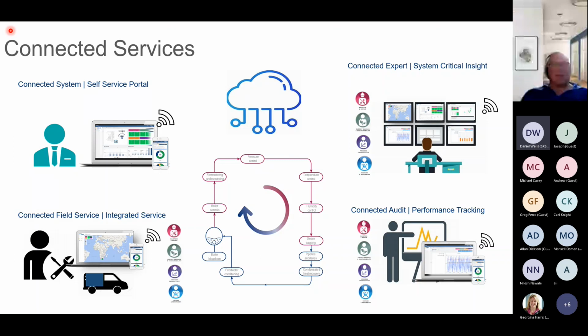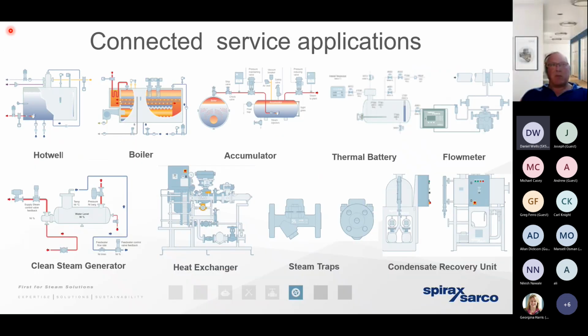So if we're able to identify a failure or an inefficiency of a component in real time, then we're able to help our client to diagnose that problem. They may have the skill set on site to be able to rectify the problem, just not necessarily to diagnose it or quantify it financially. So these gateways can be fit to any number of different steam equipment, ranging from the hot well, the boiler, even the steam battery that we've spoken about. And then at the process, the heat exchangers, the condensate recovery systems. If we're able to monitor and identify whenever a piece of capital equipment is starting to operate inefficiently, we can identify that, we can report that back to the client, and we can demonstrate a significant payback. We can reduce the demand for steam and ensure that they're moving towards net zero or decarbonisation of their steam system.